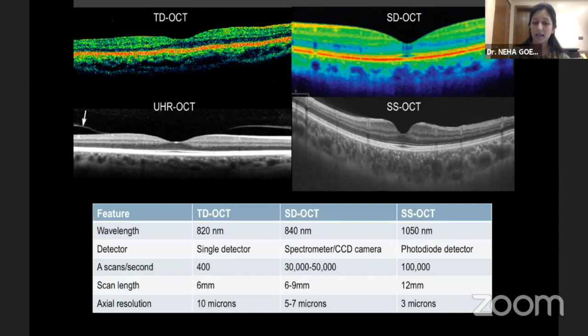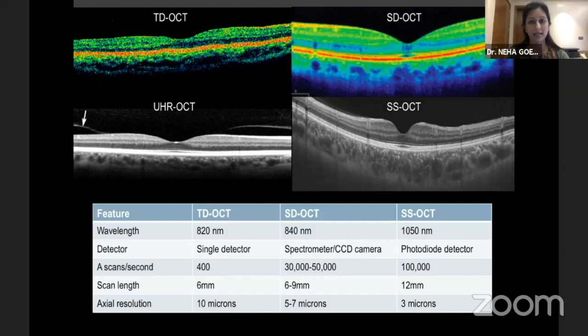So again, just revising, the wavelength is the same in time and spectral domain, whereas in swept source, we have a longer wavelength. There was a single detector in time domain replaced by a spectrometer in spectral domain, and now a photodiode detector in swept source OCT. Of course, the number of A scans per second is almost more than 10 times over these, and the scan length has also increased, allowing for a wider area to be visible in a single scan. And as I said, the resolution has been improving.